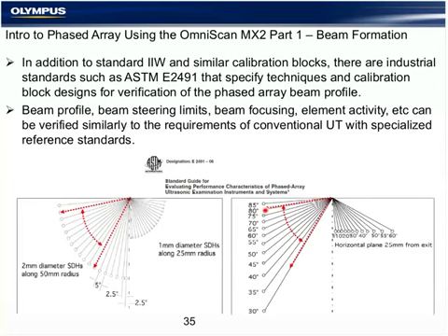The calculators would allow me to program a 20-degree beam. But if I looked at the A-scan quality of a 20-degree shear wave, it would be unusable. So, in other words, experimentation on cal blocks, more so than computers trying to predict what's acceptable to one customer or not, is how we determine and verify the useful range of what we're claiming.